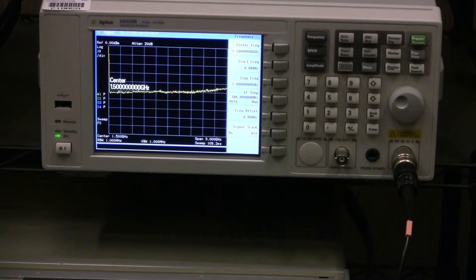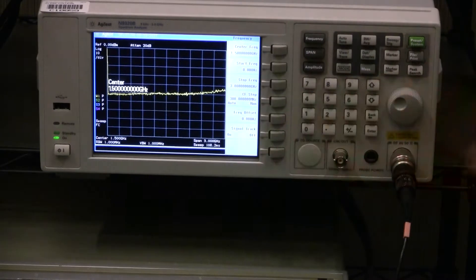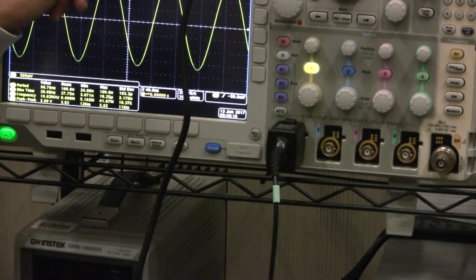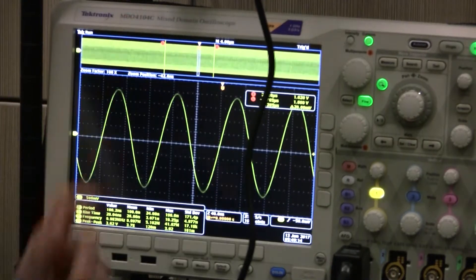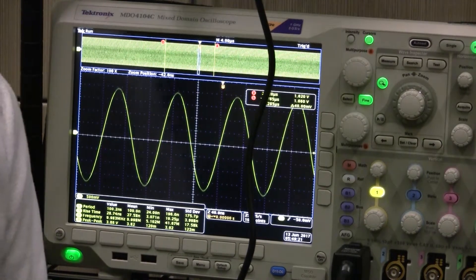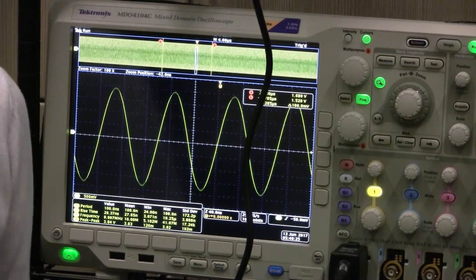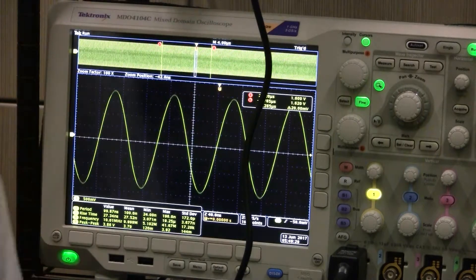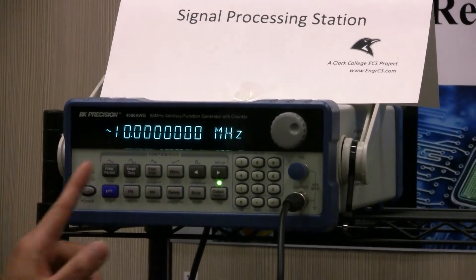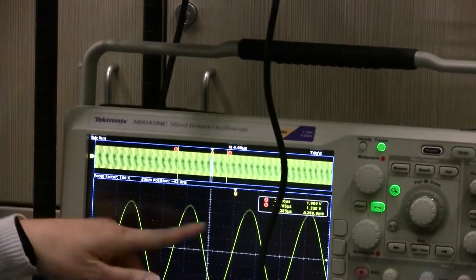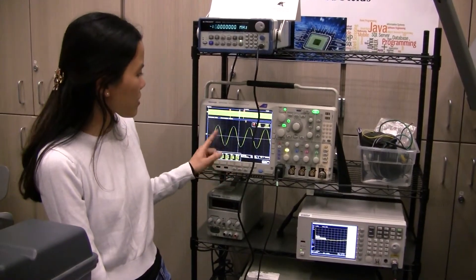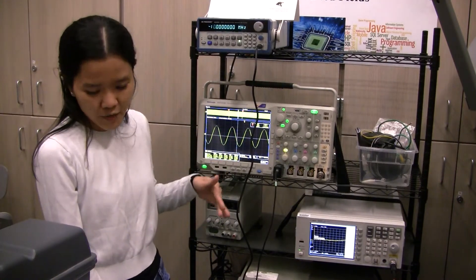It also has high accuracy power measurement and high resolution. The third machine is called the MDO4104C. This is a mixed domain oscilloscope. It includes a spectrum analyzer, function generator, logic system analyzer, protocol analyzer, and frequency counters. It can measure frequency ranges up to 3 GHz. It can display all information from the function generator, including frequency, peak-to-peak value, and period. This machine can display in both time domain and frequency domain.